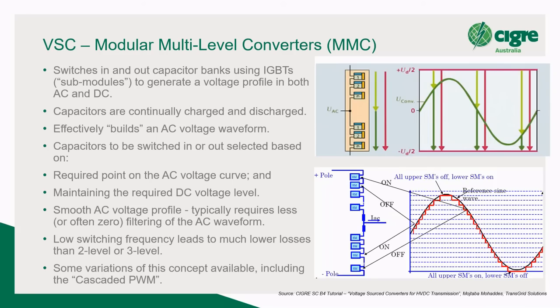But a VSC can allow you to, if you take the interconnector example, and you've got a lot of power, all the power you need available at the rectifier, provide a form of fast frequency response. And that reminds me, I did gloss over that in one of my slides, where fast frequency control is becoming an option that's being selected or specified. That's where at your receiving end, you pretty much say, well, we want you to control the frequency here, or if the frequency goes outside of a certain range, we want you to interfere and provide more power or less power, or run back your power in a way to help control that frequency. So that's like a fast frequency response.